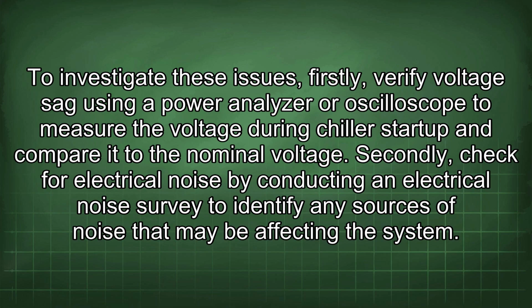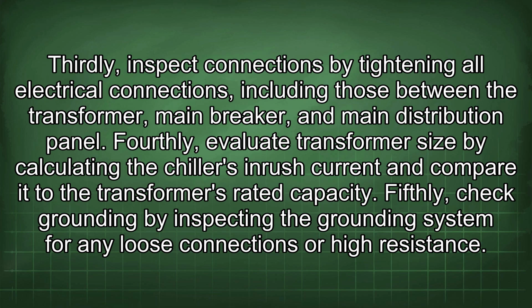To investigate these issues, firstly, verify voltage sag using a power analyzer or oscilloscope to measure the voltage during chiller startup and compare it to the nominal voltage. Secondly, check for electrical noise by conducting an electrical noise survey to identify any sources of noise that may be affecting the system. Thirdly, inspect connections by tightening all electrical connections, including those between the transformer, main breaker, and main distribution panel. Fourthly, evaluate transformer size by calculating the chiller's inrush current and compare it to the transformer's rated capacity. Fifthly, check grounding by inspecting the grounding system for any loose connections or high resistance.